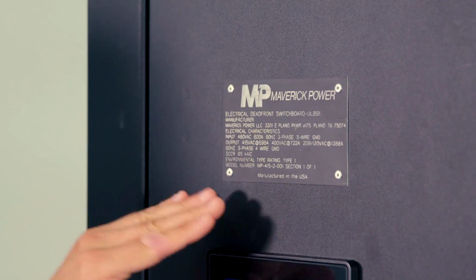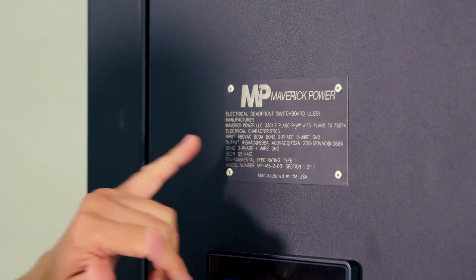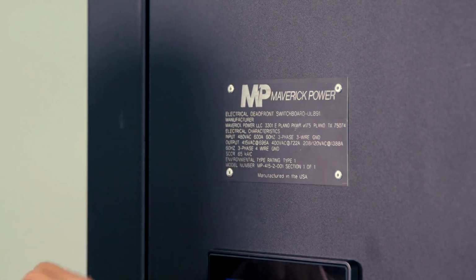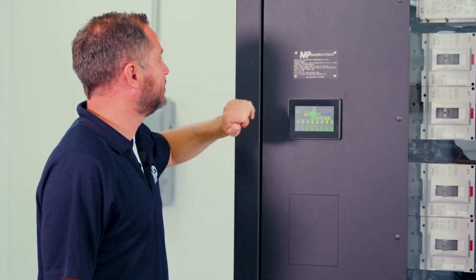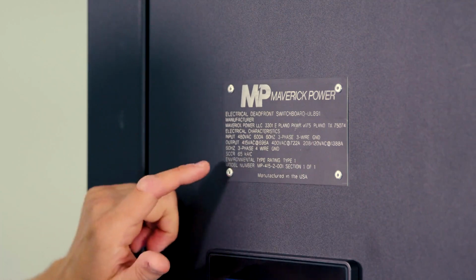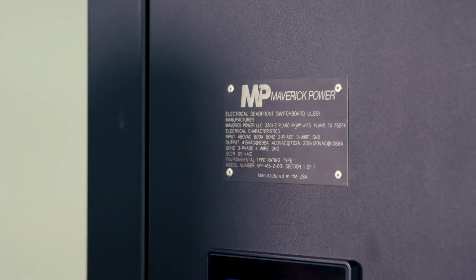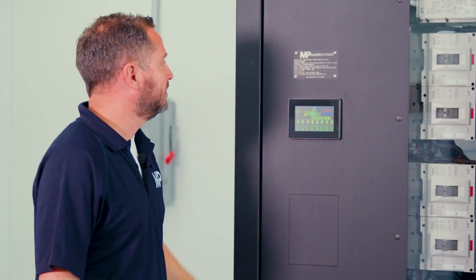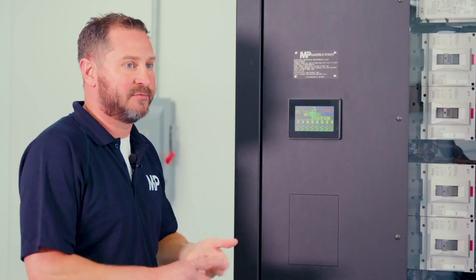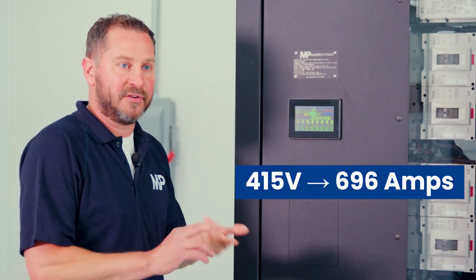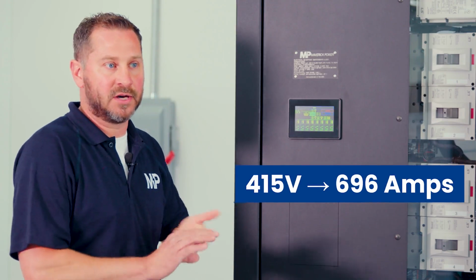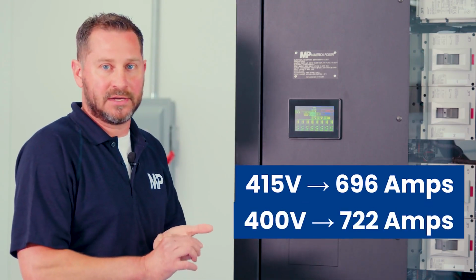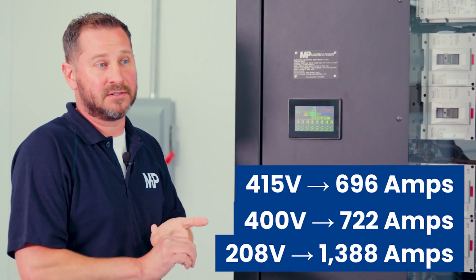This is our Maverick Power placard. This has all of our information on it. This is a UL 891. It shows our address where this was built, the electrical characteristics, the input is 480 volt at 600 amp, 60 hertz, 3-phase, 3-wire and a ground. Our output is going to be 415, 400, or 208. 415 is going to be at 696 amps, 400 is going to be 722 amps, and 208 is going to be 1388 amps.